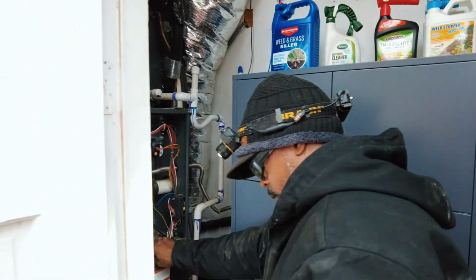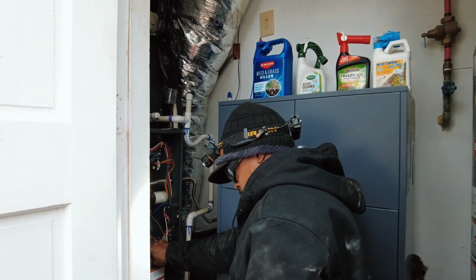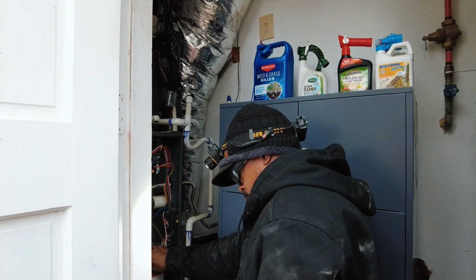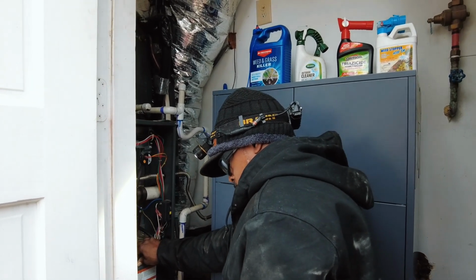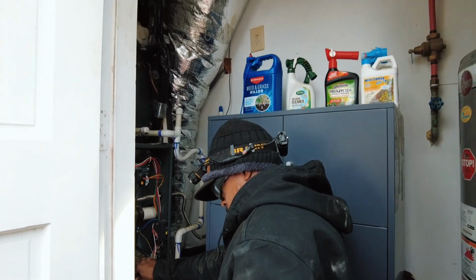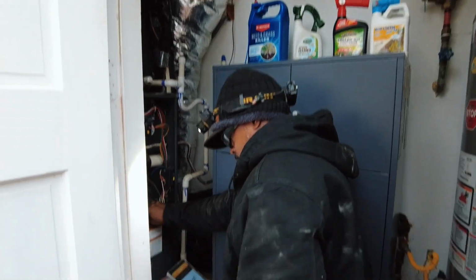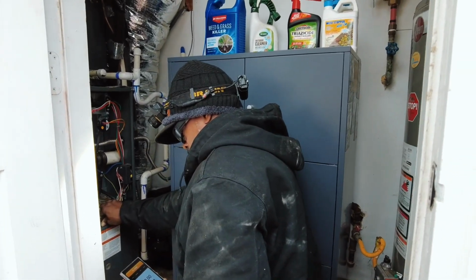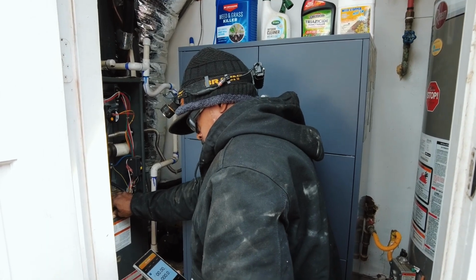Checking our amp draw here now, making sure that blower is not overamping or underamping. More than likely, with the static pressure being so high, it's probably going to have a lower amp draw than what would be rated, but we'll see.